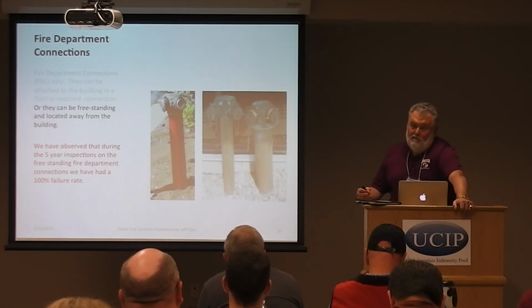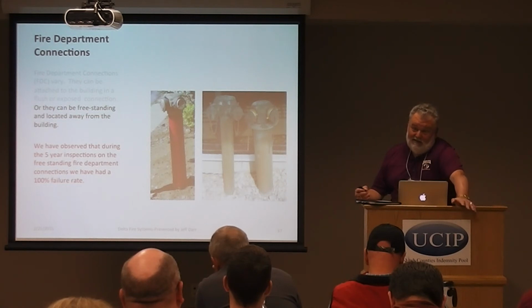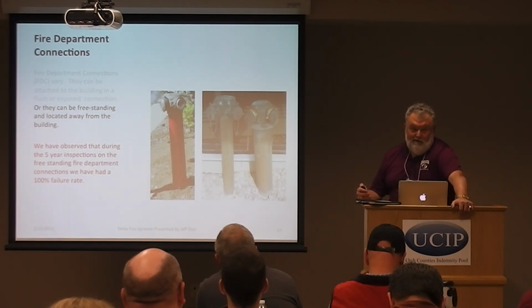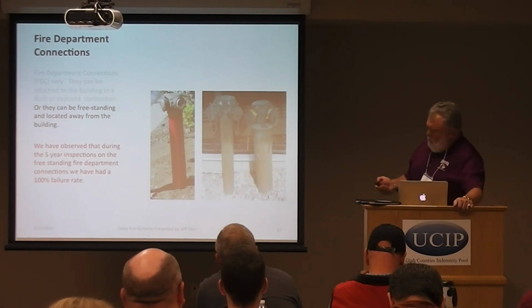You know, there's some argument that you can put these 40 or 60 feet away from the building and it's easier for the fire department. The problem is they're not maintained and tested all the time, and that underground pipe is normally dry, and if it's run in ductile iron or C900, those gaskets dry out, and the minute you hit them again, you're blowing them apart. So, personal recommendation, go with wall mounted.